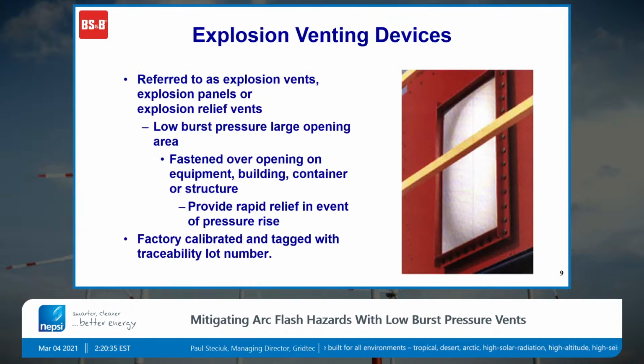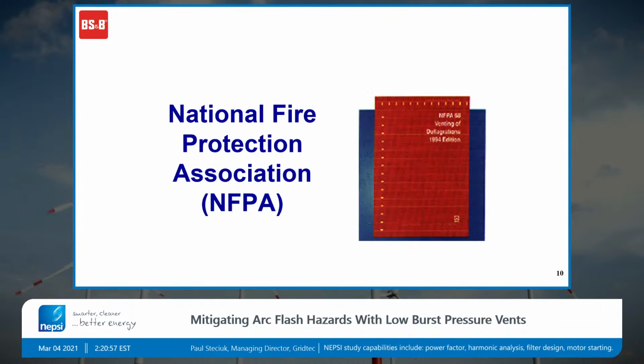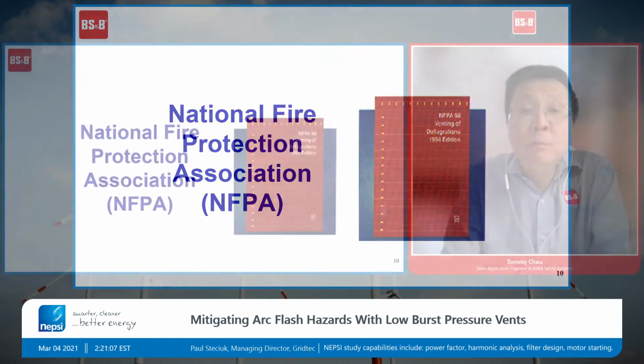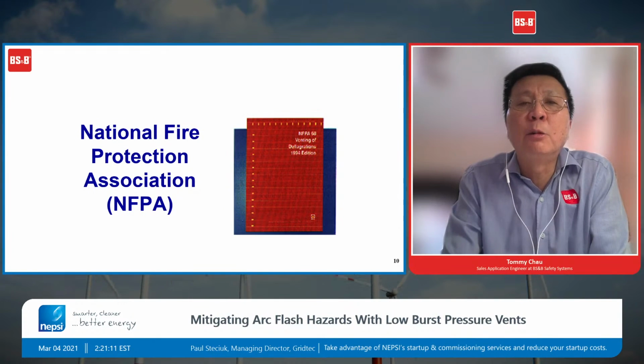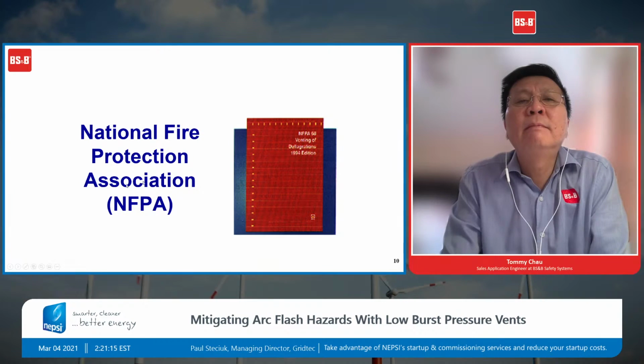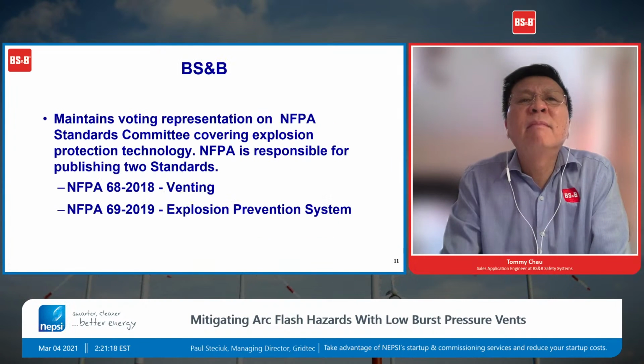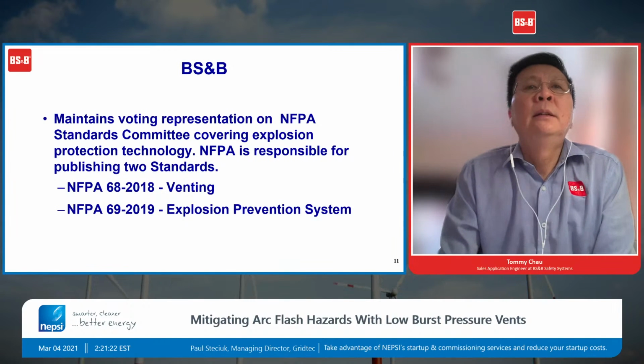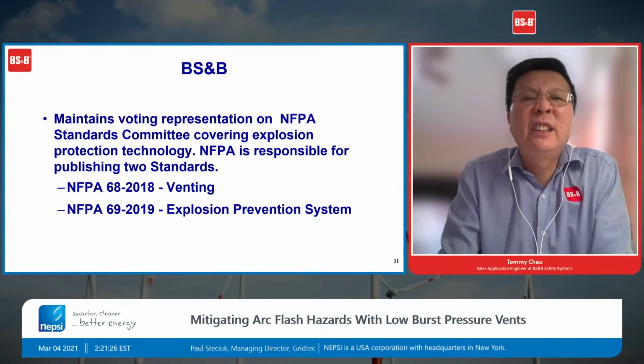Okay, so an explosion vent is a low burst pressure membrane that could be installed over an opening of different equipment. We put a lot of explosion vents on material handling equipment. It is calibrated and tested. BS&B, we are on the committee and we follow NFPA 68 to do sizing calculations to determine the net relief area required for the equipment. So BS&B has representation on the NFPA 68 standard and NFPA 69.